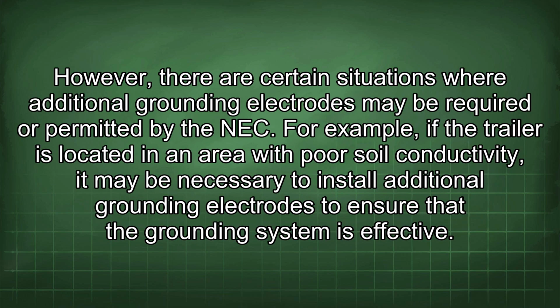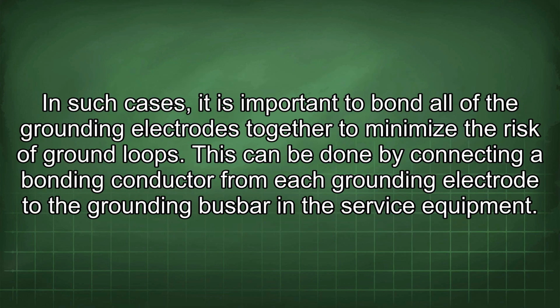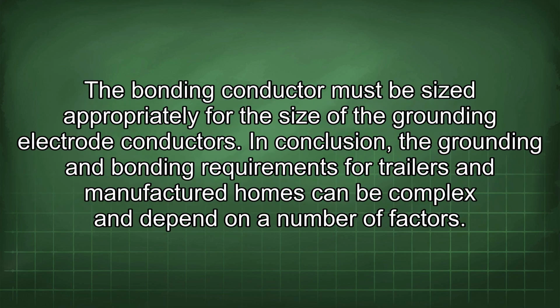However, there are certain situations where additional grounding electrodes may be required or permitted by the NEC. For example, if the trailer is located in an area with poor soil conductivity, it may be necessary to install additional grounding electrodes to ensure that the grounding system is effective. In such cases, it is important to bond all of the grounding electrodes together to minimize the risk of ground loops. This can be done by connecting a bonding conductor from each grounding electrode to the grounding busbar in the service equipment. The bonding conductor must be sized appropriately for the size of the grounding electrode conductors.